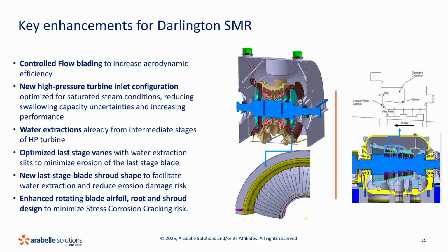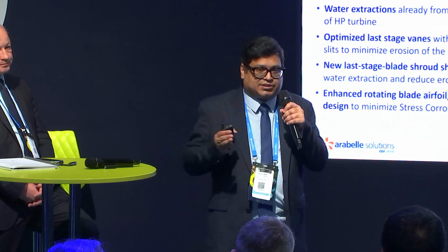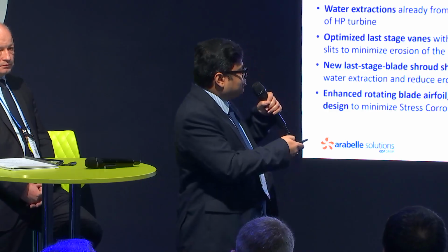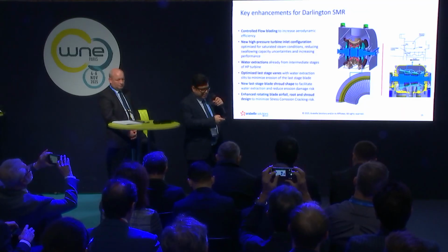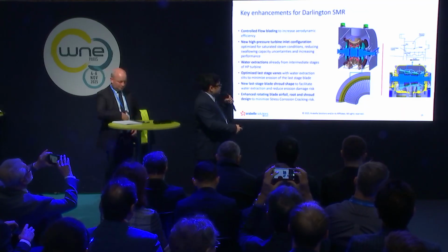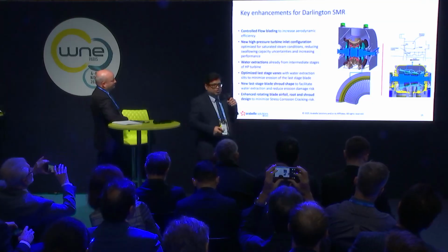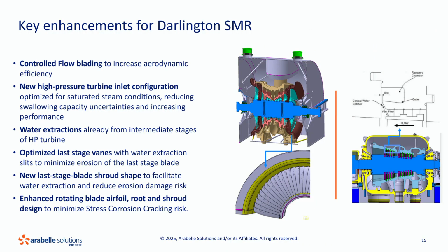We also have a new high pressure turbine with a new inlet configuration. Typically in Arabelle Solutions or legacy designs we used RADAX, radial-axial stages, but here we went back to a torus with a fully optimized axial stage, because swallowing capacity is very important for the nuclear turbine.